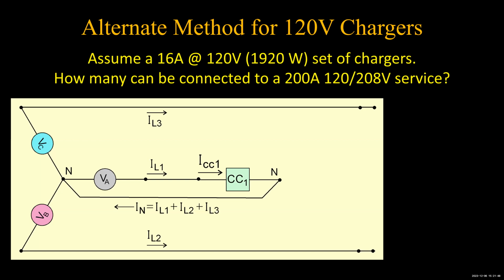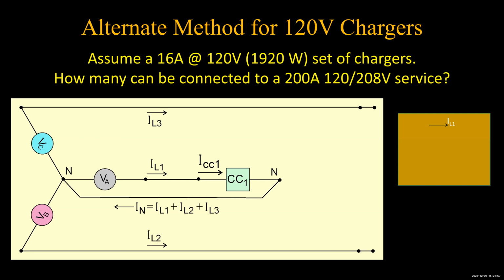Here's charge controller number 1, and it gives some current in line 1 and some current in the neutral, but nothing in line 2 or line 3. And that's going to look like this, line 1 current. And now we add another charge controller here, and we got charge controller current. So now we got charge controller 1 and charge controller 2 current, both coming into the neutral. And there's your line 2 current. And the sum of those two gives you the neutral current. And you have to add them point to point, or vectorially, or as phasors, or whatever you want to call them. And you see the neutral current is equal to the line current when you've got an unbalanced load.